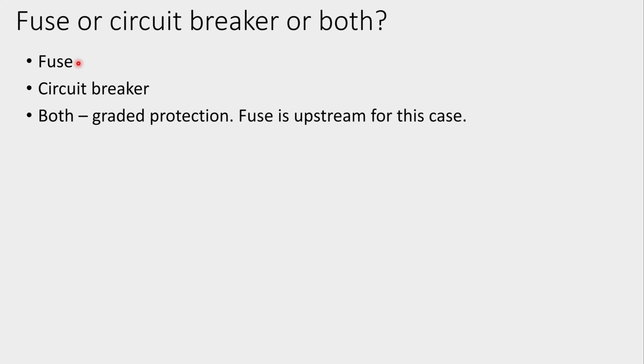If I am going to use a fuse, then the fuse must be very close to the battery. The problem with a fuse is if the user overloads the unit or there's a fault, then the fuse breaks. Then what often happens is the user does not go and buy another fuse, they just bypass it. So fuse is not ideal. A circuit breaker, on the other hand, allows me to use it repeatedly. So it's unlikely that the user would remove the circuit breaker, because the circuit breaker can be reused. Now, what you could do is also use a fuse and a circuit breaker, but then the fuse must be higher, a higher current rating than the circuit breaker. So only if the circuit breaker does not trip, then the fuse will trip right by the battery.